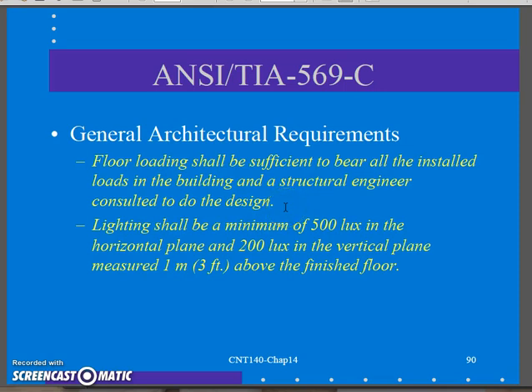Floor loading: there should be thought given to whether the floor will support your routers, switches, and servers in your rack. Building plans should be consulted, and possibly even an engineer, to know if the floor loading of the building will handle all the equipment you're going to put in there. One of the other reasons you do rack drawings is to figure out what's going in there and how much weight will be on that footprint on the floor.